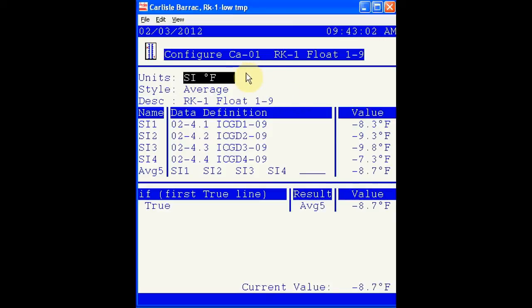Units is used to define the output of the calculation. Because we want the average of 4 sensors, and we know that average will be in degrees Fahrenheit, the units is set to SI, meaning sensor input, degrees Fahrenheit. Style allows you to define what the calculation will be doing. An optional description can be programmed here. As you can see, 4 sensors are listed and the average is found. For the calculation to be effective, the result must be correct, and the current value will be reflected here.